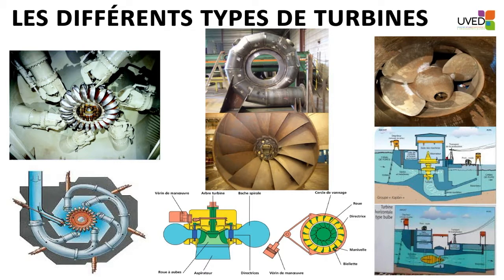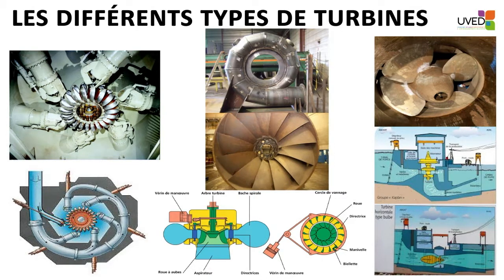Here we see the core of the hydroelectric plant — the turbine. Depending on the head, the turbine type is entirely different. For high head systems, the turbine will be of the Pelton type, shown on the left-hand side picture — turbines rotating in the air that are only pushed by the water jet hitting them. If the turbine is inside a housing so that water doesn't spray everywhere, one needs to remember that the push is exerted by the water directly on the turbine, a bit like the small windmills we used to build in rivers when we were children.